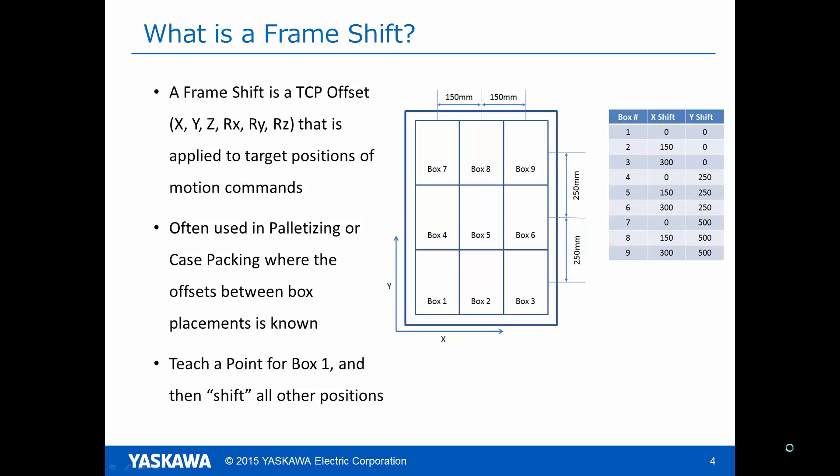A frame shift is simply a TCP offset that applies to the target position of a motion command. Frame shifts are often used in palletizing and case packing where the offset between product placements is known. For example, the picture on the right shows a pallet with nine boxes on it. In this case, a position could be on the top of box one, and the same target position along with a frame shift could be used to move to the top of the other boxes.